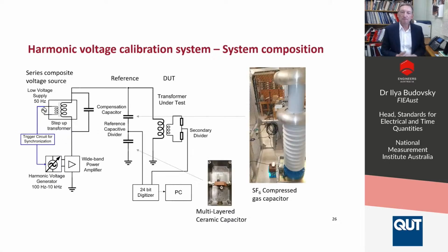So here's the schematic of the system. Again, we have two synchronized sources, a 50 hertz source and a harmonic source up to 10 kilohertz. The 50 hertz source feeds a step-up transformer that produces the high voltage, and the harmonic generator feeds a wideband amplifier.